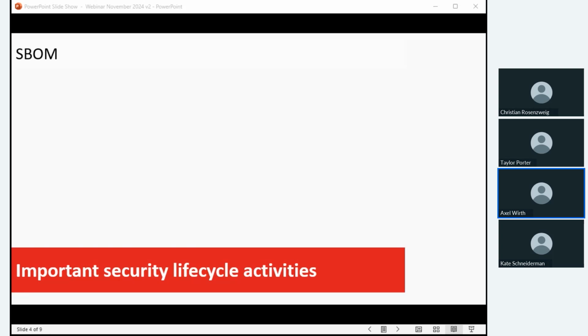From the hospital side, obviously, first of all, the operator needs to have access to the respective SBOM, and that is both a technical sharing challenge, but also a legal and access rights challenge. Hospitals have hundreds, if not thousands, of devices on their networks. They come from dozens, if not hundreds, of different manufacturers. So their library of SBOMs over time will become very large, and then they need to be able to correctly match the SBOM version to the correct device, which again, because of complexity, can be quite challenging. Once you're past that, you then need to use the SBOM to identify the vulnerabilities via public vulnerability databases. And unfortunately, depending on the vulnerability database you use and the matching algorithm used to match a software component name in your SBOM to the component name in the vulnerability database, you may actually end up with a different list of vulnerabilities than the manufacturer does.